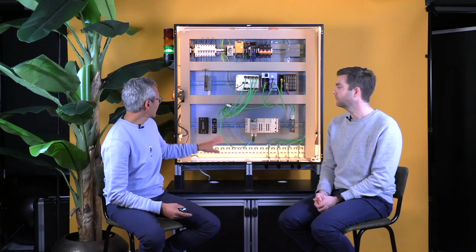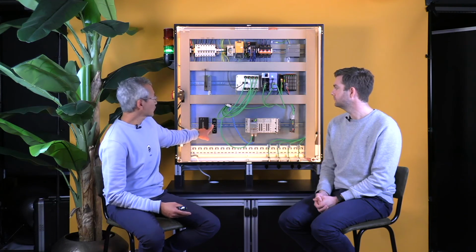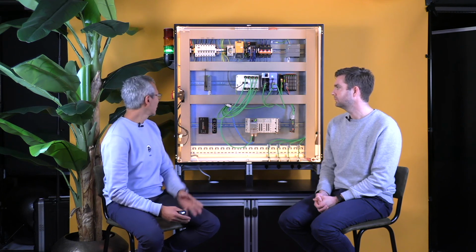What you can also do is put a so-called EtherMirror in, and with this EtherMirror you have a permanent connection open for your EtherTap. Okay, so this is fundamentally a measuring point that allows you to get passive monitoring data without disturbing or breaking up your network. Exactly. And you have all the benefits of the timing, jitter and update times, alarms, and protocol-specific information.